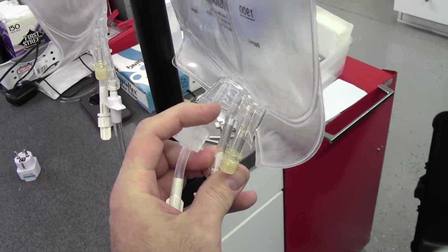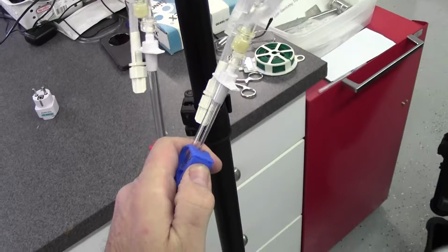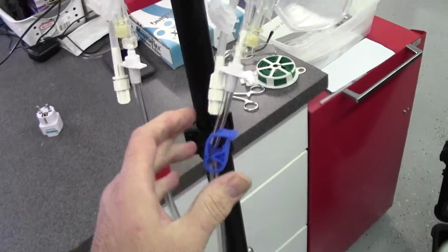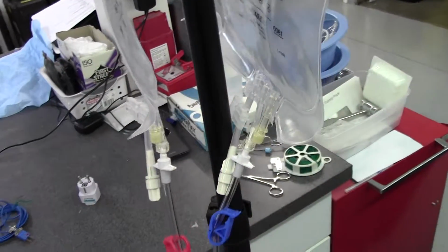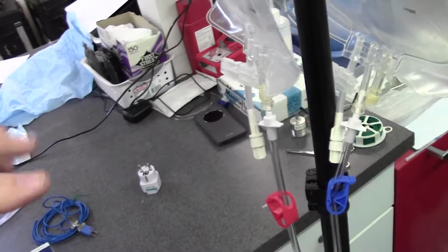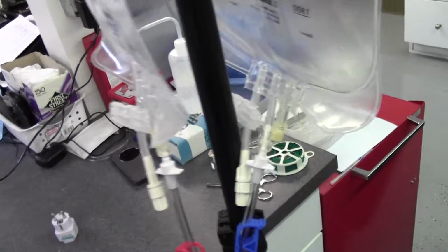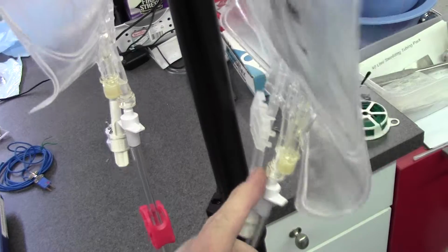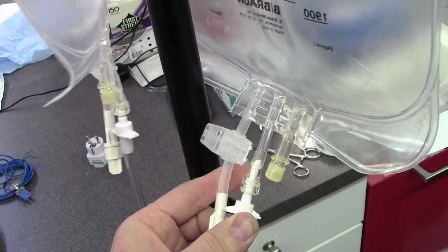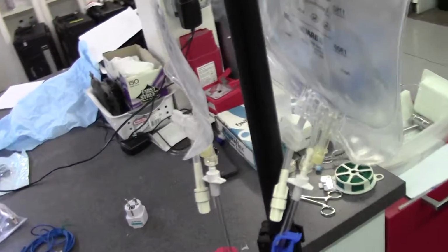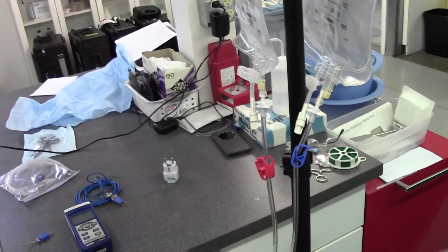You start to see a little air drop in, and you're going to want to clamp this off at that point. And then you can remove the bag, set it on the table, get another bag out, and do the transfer by removing the pin and then pinning the next bladder and rehanging it. Then you have to adjust the height of the bladders on the stand in order to get the pressure.